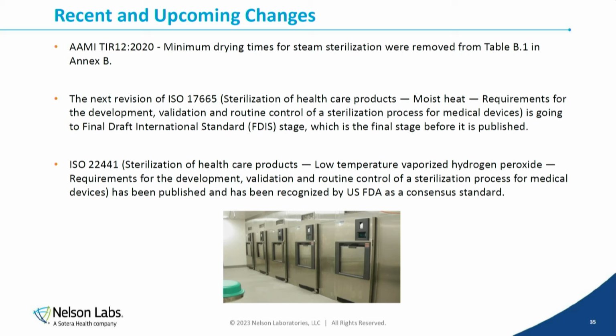These are some of the recent changes that are going to happen for standards that you probably want to look at for your instructions for use as well. I won't go through the changes because it's written up here, but we have a new VHP document, and we don't have dry times anymore. They used to write dry times in the table. They've taken it out. So now you have to determine what the dry time for your product is. So if you have a big case, the highest we've seen is 70 minutes. Don't go past 70 minutes. Hospitals are not going to do past 70 minutes. So if you can't make your dry time in 70 minutes, that means reconfiguration of the tray, or you are placing your instruments in a way that steam can penetrate easily in and out, okay? Lumens facing the walls, things like that.